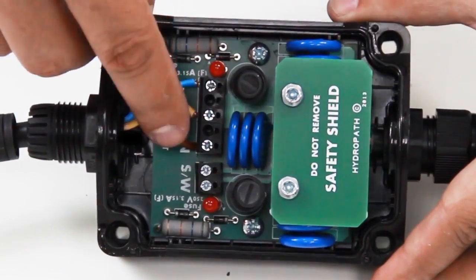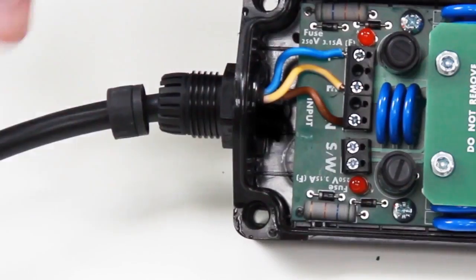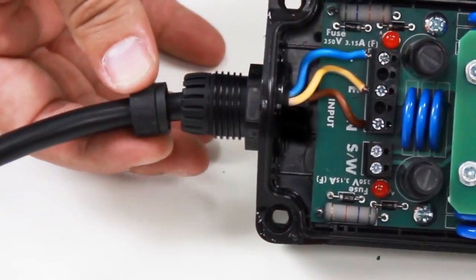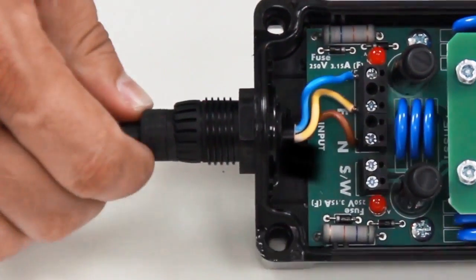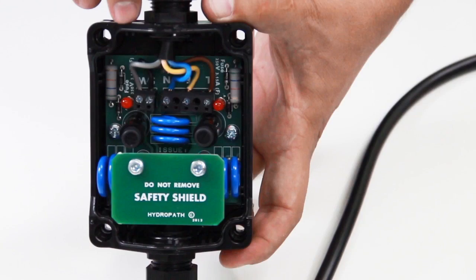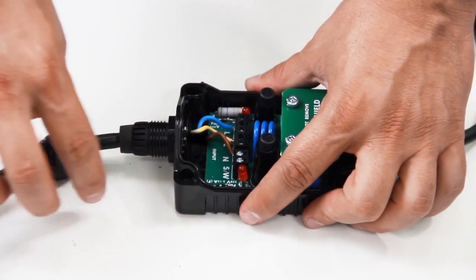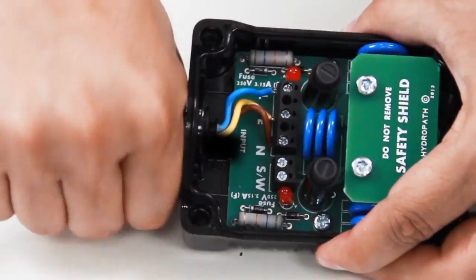Connect a new 3-wire standard cable. Make sure to take the rubber seal from the supplied cable and place it on the new cable. In case you are required to connect the unit to an indicator light, computer or alarm, use a 5-wire cable and connect it to the SW connection as well. Insert the rubber seal into the grommet and screw the gland.